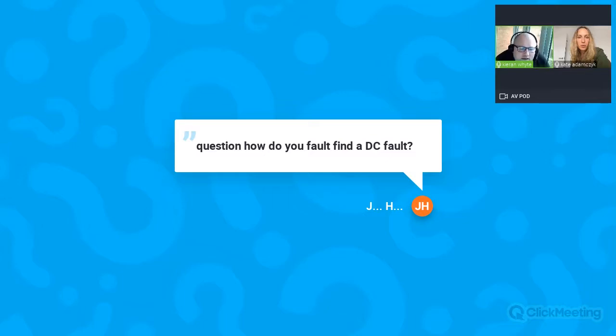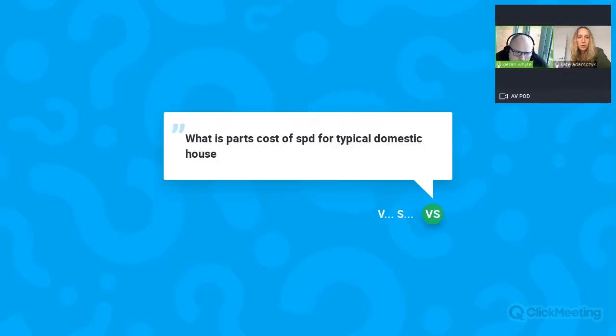I see another question there about SPDs. Within a domestic property, because you wouldn't normally have a lightning protection system, a Type 2 should be sufficient on the incoming ways. With Schneider Electric's residential domestic consumer unit, the Easy9, we provide an overcurrent protective device for the SPD. So in the case of end of life or any servicing, you can isolate it without having to isolate the whole circuit.